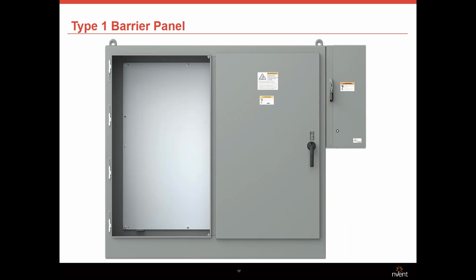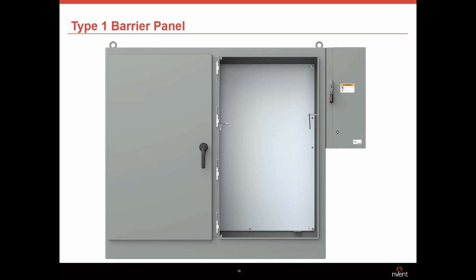To demonstrate the value of the Type 1 rated barrier panel, if one door of the enclosure were to be opened, say the one that's open in this illustration, the other bay of the enclosure would remain an enclosed UL Type 1 enclosure. If the first door were closed and the other door of the enclosure were to be open, the other bay of the enclosure with the door closed would remain a UL Type 1 enclosure. So as long as the door is closed and all of your surfaces are completely enclosed, it will remain a Type 1 enclosure.